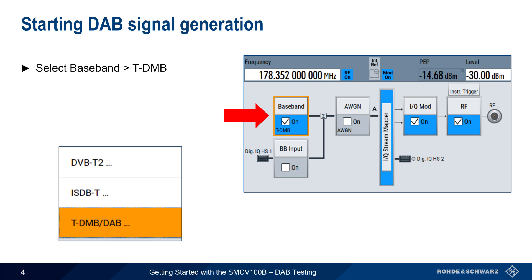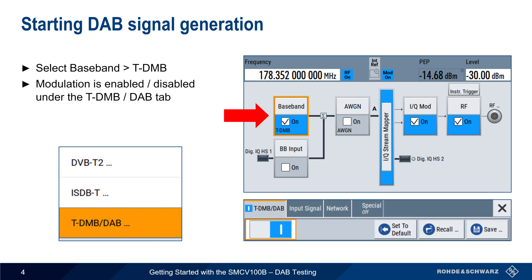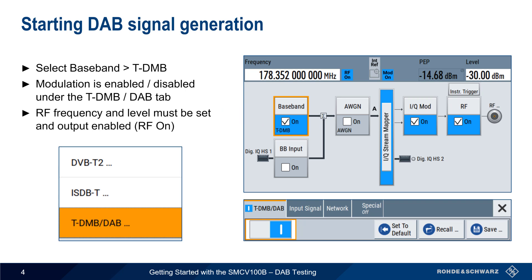Clicking on this block will bring up the TDMB DAB dialog, and a simple toggle switch is used to enable or disable DAB modulation. Note that like all other signal generation tasks on the SMCV, both the RF output frequency and output level must be set, and the RF output block must also be turned on.